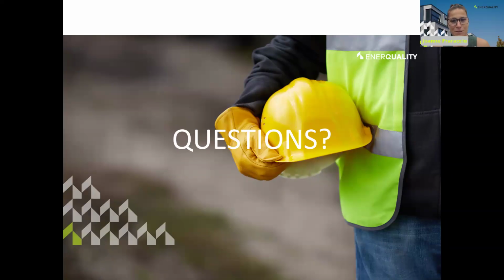One has to do a little bit with the SB12, so I'm going to have you review this one carefully. In Ontario, SB12 Section 3.1.1.126A requires drain water heat recovery units to be installed vertically within 5 degrees. You mentioned that horizontal installations are possible. Are those actually permitted here or only in other jurisdictions? If they are used in Ontario, is that typically through an engineered equivalency or manufacturer certification? And if so, is that documentation publicly available or accessible for review?